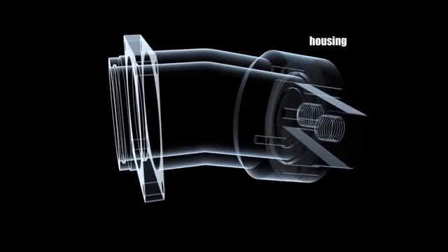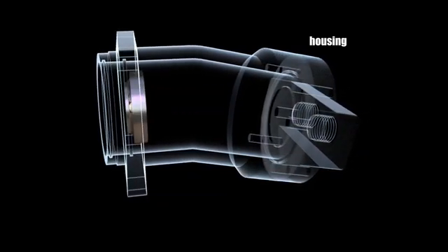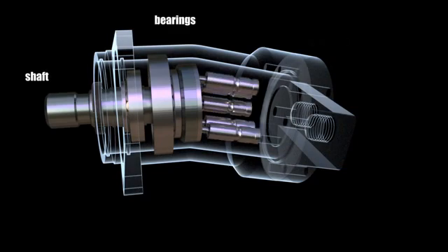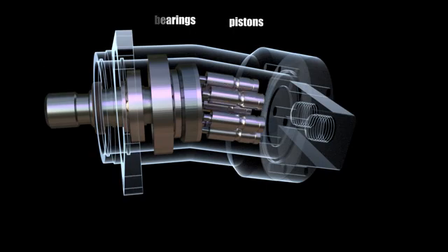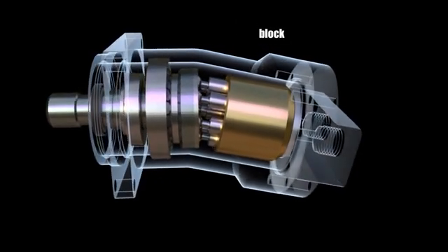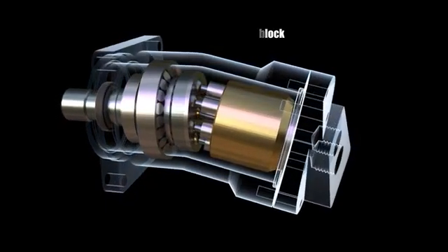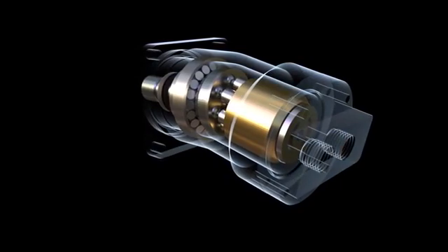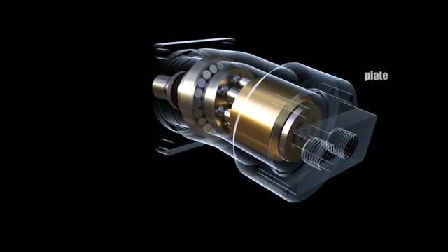The pump housing has a distinctive curved shape, and its shaft is supported by bearings. The pistons are attached to the shaft with spherical bearings and placed into the inclined block mounted on the axis. In the pump shown, pistons are used to transmit the rotation from the drive shaft to the block, while some other devices use cardan shafts as a drive unit. The block is supported by a valve plate that has a spherical surface. The plate has channels for supplying and discharging fluid to and from the pistons. The fluid leaves the valve plate and then enters the cover that has an inlet and outlet opening.